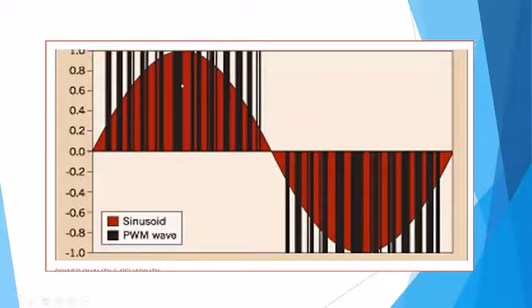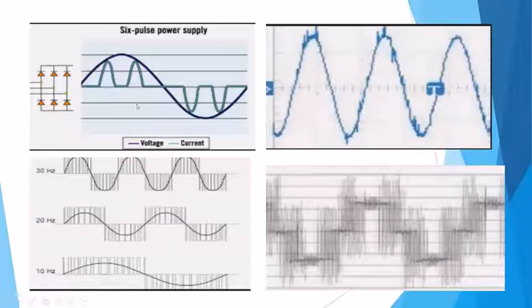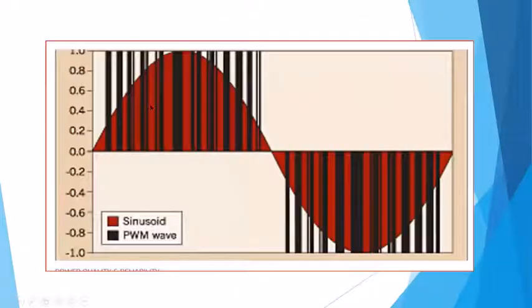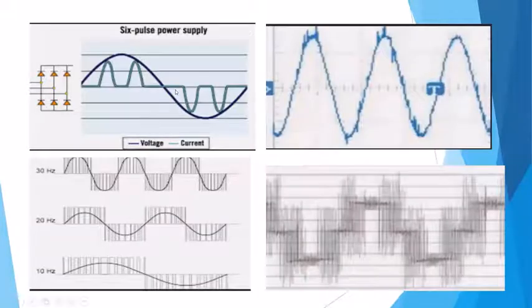Then they went to like 1,500 pulses. Now they're up as much as 5,000 to 6,000. They're not really audible, you can't hear them with a human ear, but they're going as much as 15,000 to 20,000 pulses now on very, very good inverters, to get these pulses exactly what we need to give you a very good current waveform. So here's more of an idea where the diodes are firing the pulses. The resultant factor of that is that the same understanding of technology of PWM is what was developed for radios. And so that all creates variable additional frequencies that end up happening as a result.